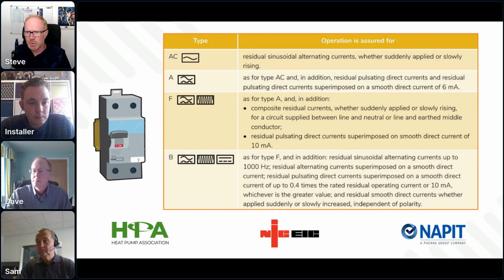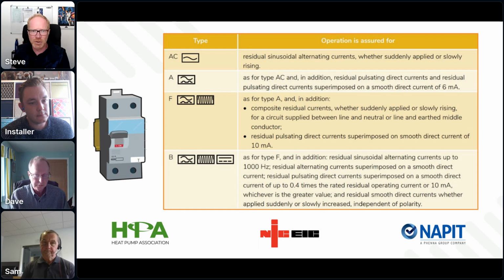If we're dealing with normal pulsating DC residual currents, that is what we know as half rectified DC, often described as pulsating. It's current flowing in one direction with periodic pulses. We find this quite commonly in a lot of electronic equipment: washing machines, simple power supplies, basic rectifiers all have this simple DC current. When we talk about composite residual currents, which are more suited to the type F and type Bs, this is a combination of AC residual currents, pulsating DC currents, smooth DC currents, and mixed frequency components. So we've got higher harmonics in it.